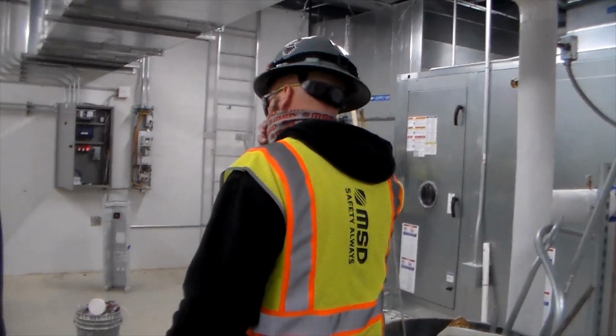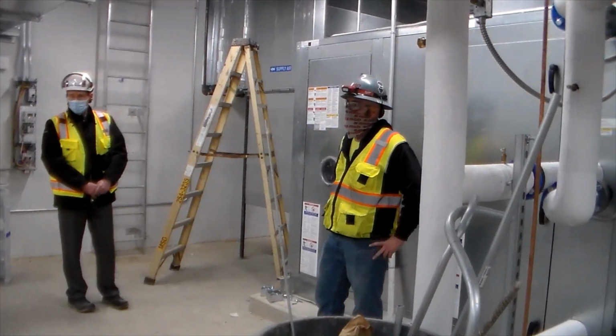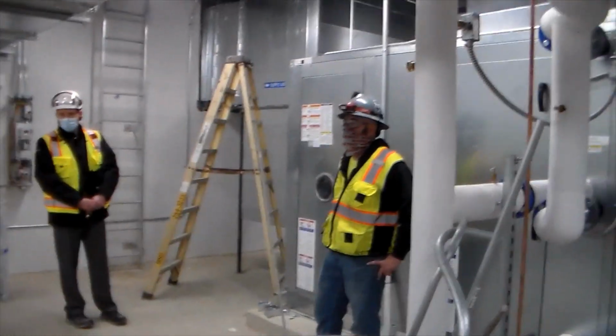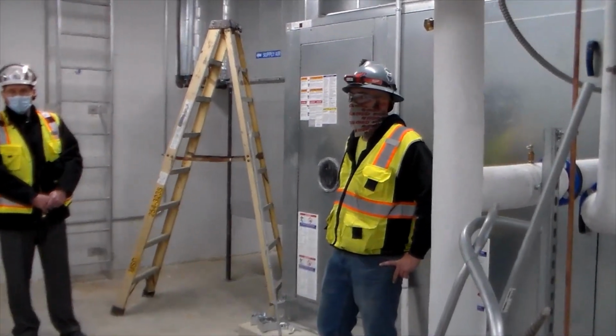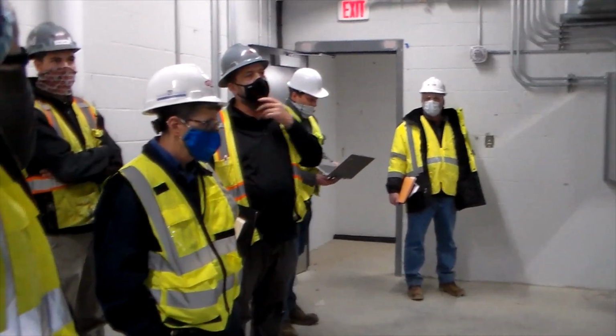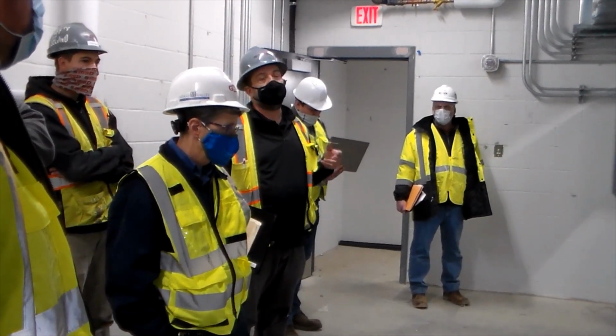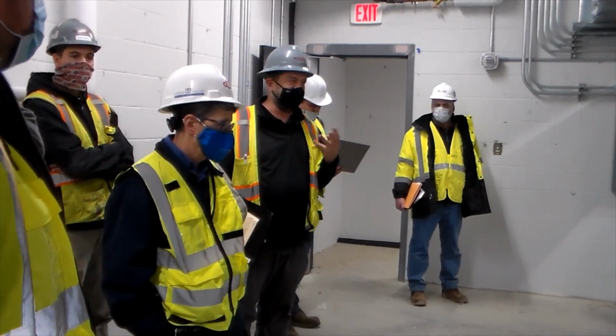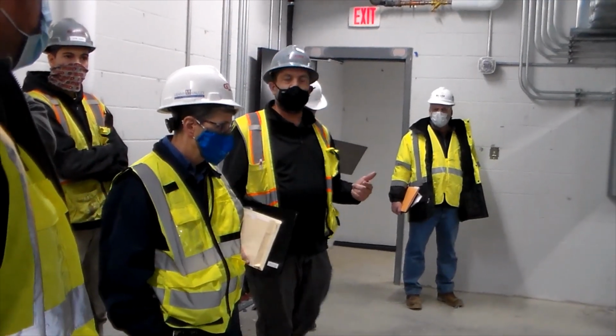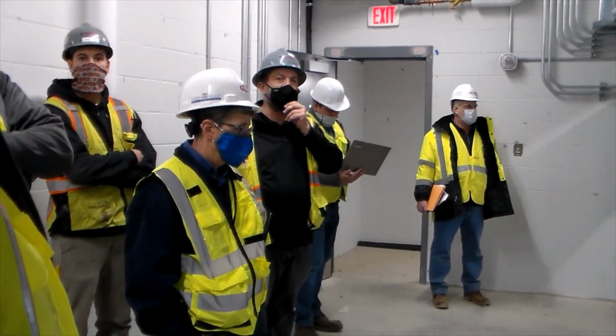And you're setting a minimum like 10% or 5% on the outdoor air? Typically they get 50, 20, it just depends on how many CFM the outside air will require. And then also you have CO2, which plays a role. Those are probably the two biggest. There is also demand ventilation, and also we add air if the exhaust fans are running. So it depends on the combination of those as to how many CFM the unit's delivering.